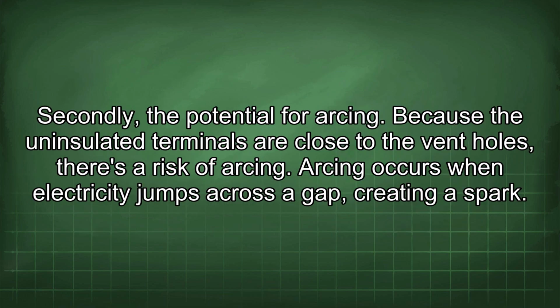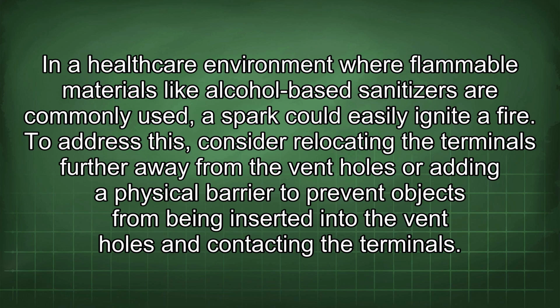Secondly, the potential for arcing. Because the uninsulated terminals are close to the vent holes, there's a risk of arcing. Arcing occurs when electricity jumps across a gap, creating a spark. In a healthcare environment where flammable materials like alcohol-based sanitizers are commonly used, a spark could easily ignite a fire. To address this, consider relocating the terminals further away from the vent holes or adding a physical barrier to prevent objects from being inserted into the vent holes and contacting the terminals.